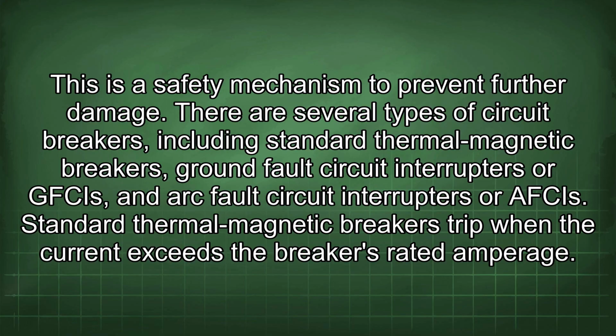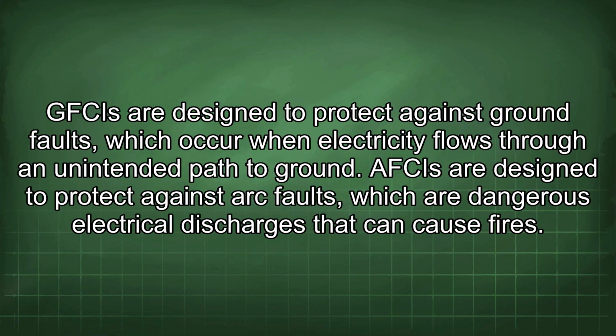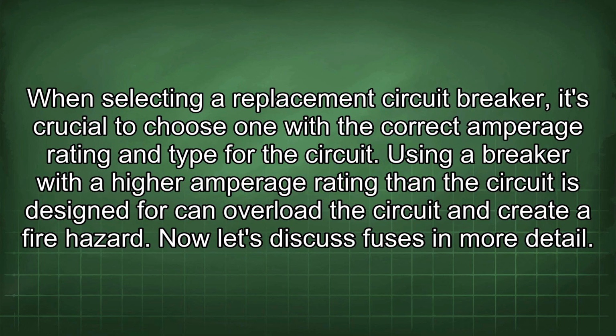Standard thermal magnetic breakers trip when the current exceeds the breaker's rated amperage. GFCIs are designed to protect against ground faults, which occur when electricity flows through an unintended path to ground. AFCIs are designed to protect against arc faults, which are dangerous electrical discharges that can cause fires. When selecting a replacement circuit breaker, it's crucial to choose one with the correct amperage rating and type for the circuit. Using a breaker with a higher amperage rating than the circuit is designed for can overload the circuit and create a fire hazard.